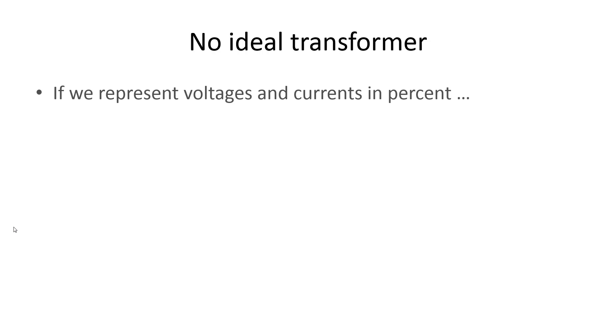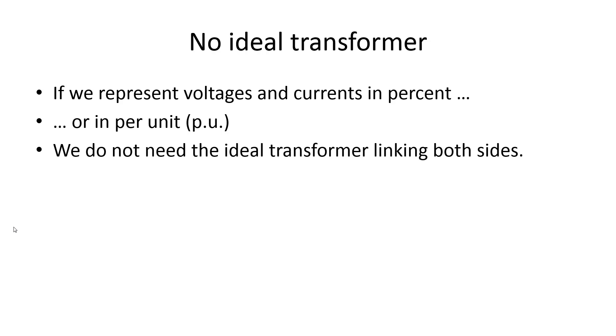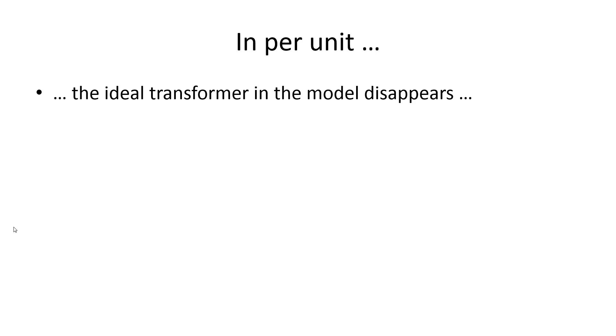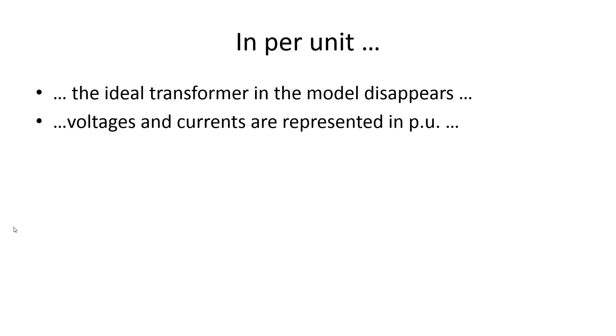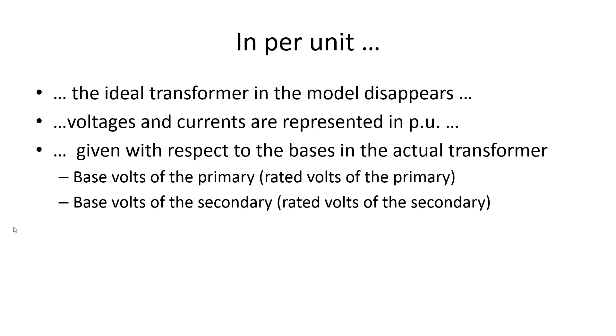Conclusions: if we represent voltages and currents in percent or in per unit, we do not need the ideal transformer linking both sides. This is no minor gain when we need to solve a national electric power grid that has thousands of transformers in it, or even in a humbler exam-type circuit with three or four transformers. When we use a per-unit system, ideal transformers in models disappear.